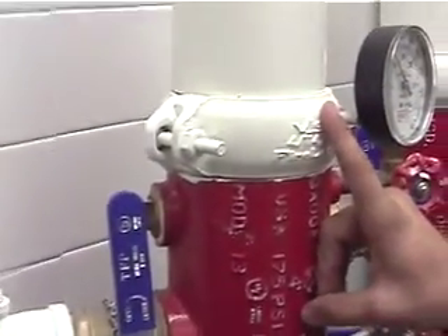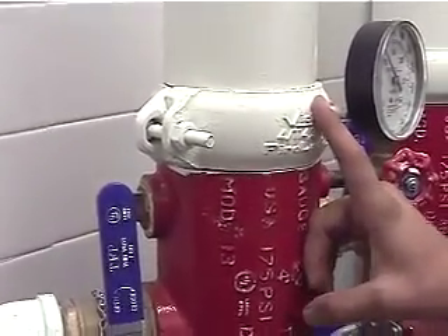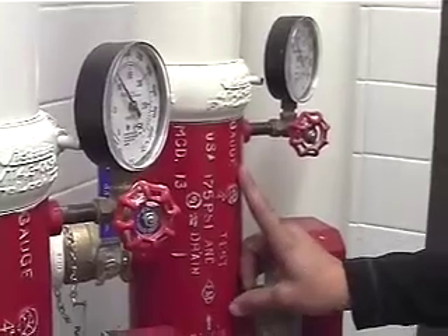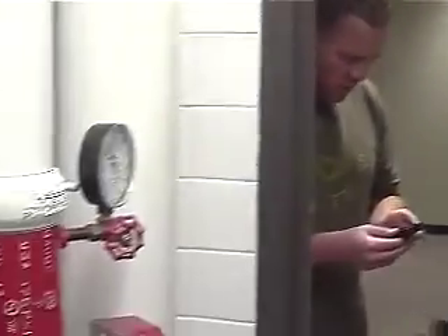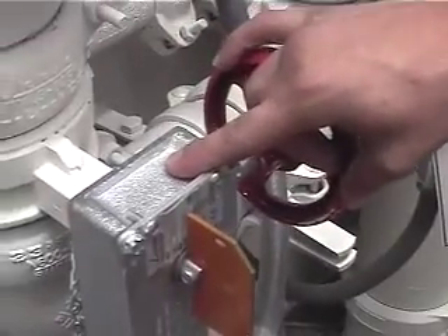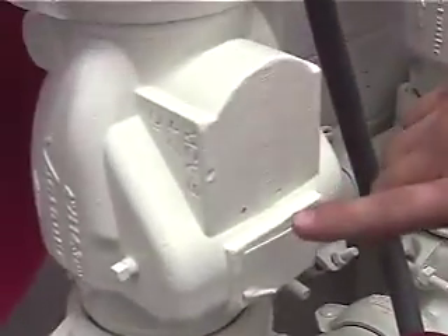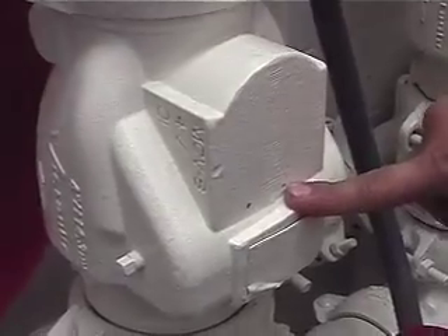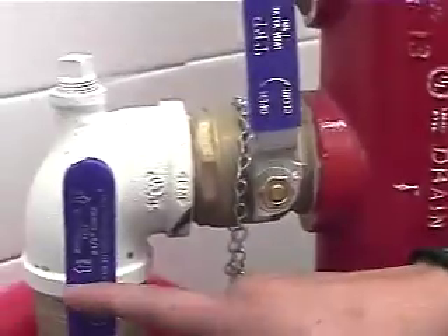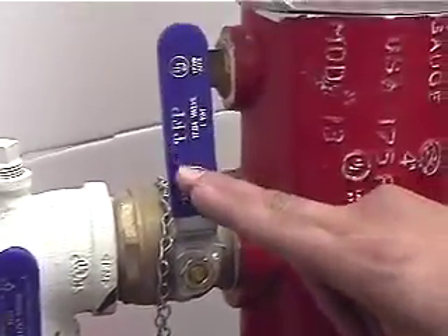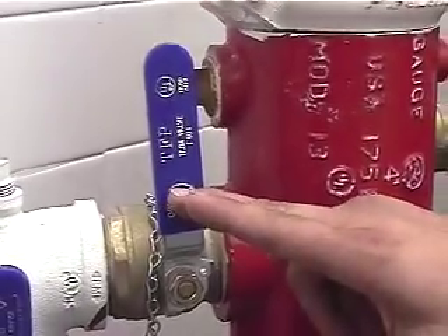The one on the left is going to be the atrium zone. The atrium is on a different smoke zone, and this will control all 3 floors of the atrium. This is for the first floor, all 3 wings, including the middle wing, except for the atrium. You'll have an isolation valve right here, another isolation valve right here for the atrium zone. This is going to be typical in all your risers. You're going to have a check valve right here, and then another inspector's test, and another main drain that still discharges on that east side of the building that we looked at earlier.